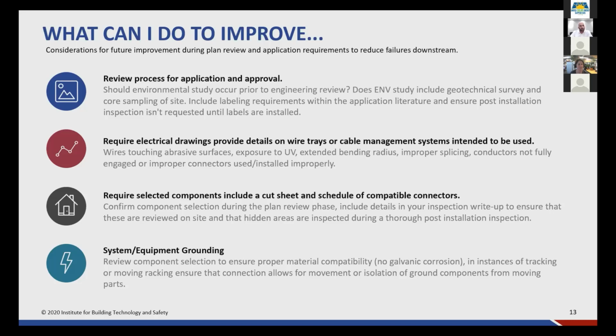Require electrical drawings to provide details on wire trays or cable management systems intended to be used or approved for use on site. This is not a 'what if,' this is a guaranteed consideration. Wires are part of the system, and the idea that during plan review or our three-line drawings we have no detail and leave it up to that 'qualified individual' who has no budget to buy additional materials and no authorization to change the work scope, to somehow manage that on site — no, that needs to be figured out on the front end and included in the electrical drawings and application requirements.